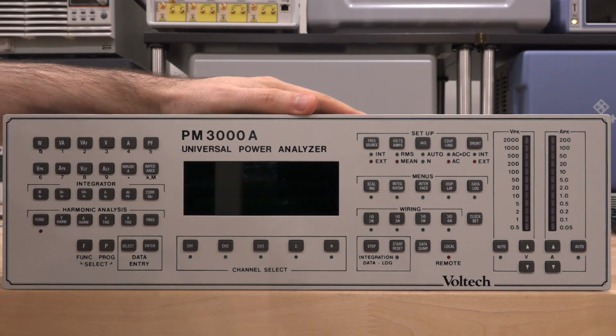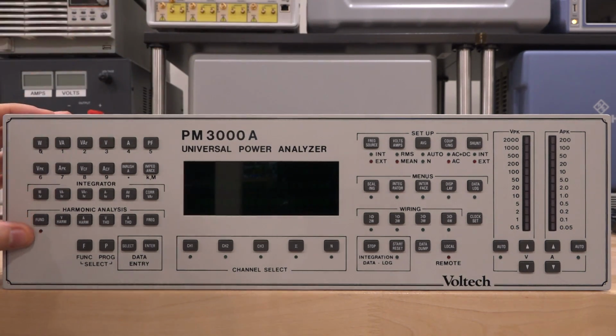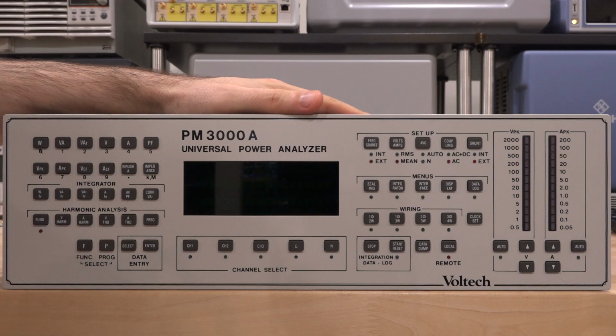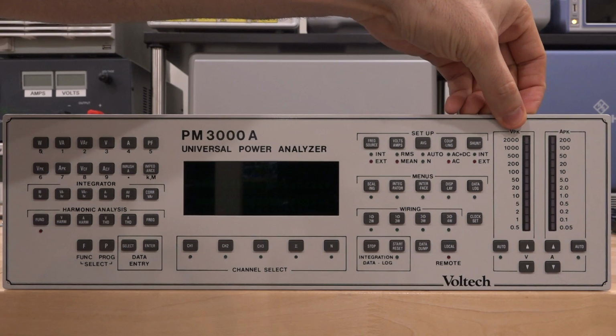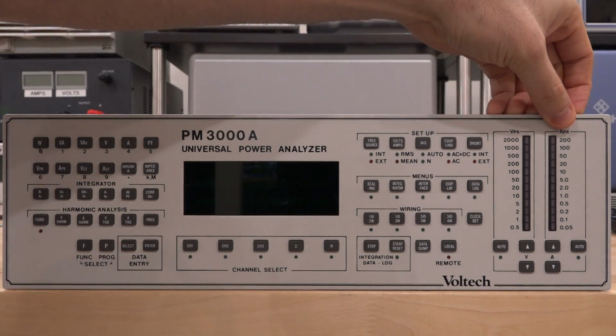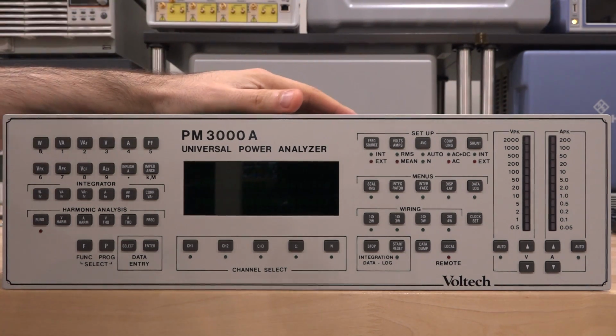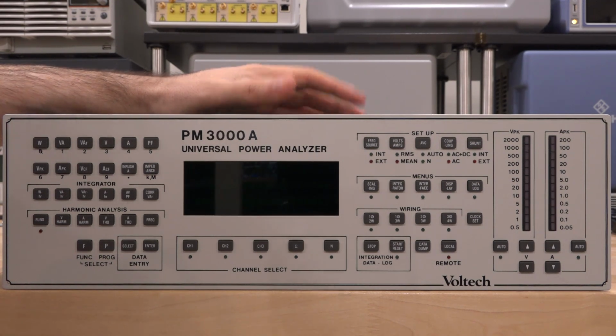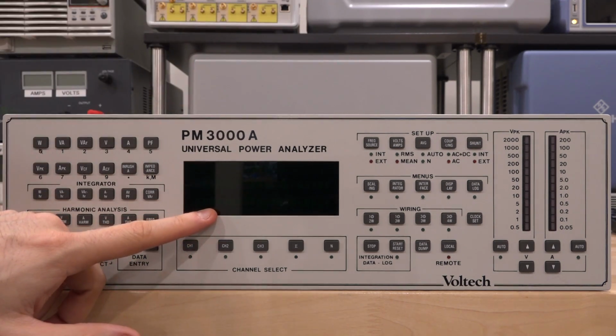And aside from doing basic power analysis, you can also do harmonic analysis, and it can give you a whole bunch of information about the nature of different loads that you connect to it. It also has a really wide dynamic range. You can see it goes all the way to 2000 volts peak and 200 amps peak, and you can capture those in fairly small spikes. So for example, for motor control or power on, power off conditions of things, you can catch those events. And yeah, it looks nice. It has a little VFD display in the front.